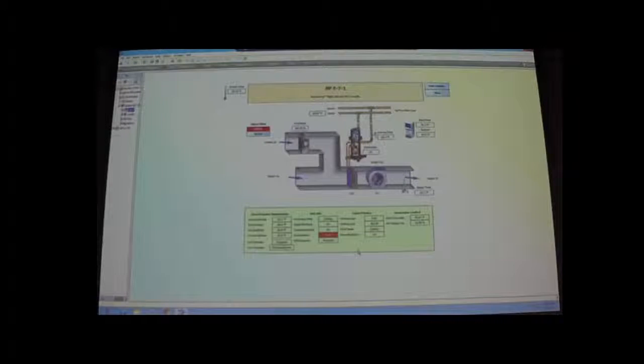So what makes the decision on that outside air damper when it's open and closed? Basically, what they had us do is the heat pumps themselves have 2 positions of cooling. So they have like a Y1, Y2, like a standard thermostat does. And basically, they had us rewire the cooling call to Y2, and then we're almost just doing Y1 as stage one, which would be the economizer.